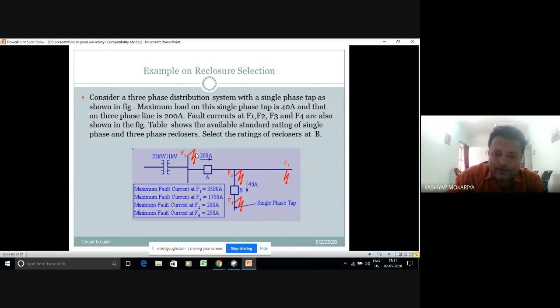See here F1, F2, F3 and F4. All the currents I have specified are the maximum fault currents. So once you are going into a design part, you should know the minimum fault current and maximum fault current at every location. Now we have been asked to find a recloser rating at this particular breaker at the junction B. So how are we doing it?